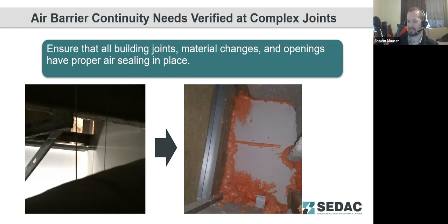What we were seeing was that the building had very poor humidity control because the heat pump couldn't keep up with the load. In the winter, the heat pump was able to keep up, but it was using so much electric backup heating that utility bills were out of control for this facility. Once we found this problem, we went in, sealed it up, and tracked the utilities over time. I'm not sure what the result was, as I left employment with this particular agency before I found out. But from talking with the people who remained, I do know there was a significant reduction in energy consumption and a significant improvement in the comfort of the occupants in that space.